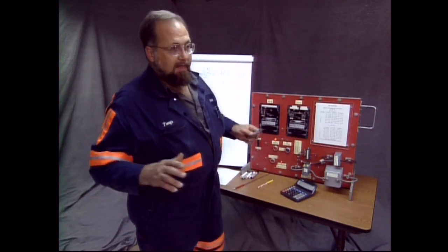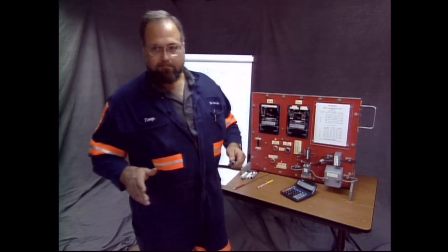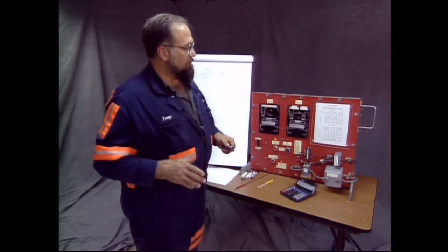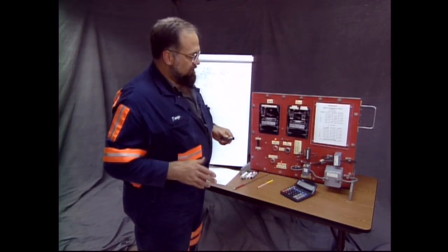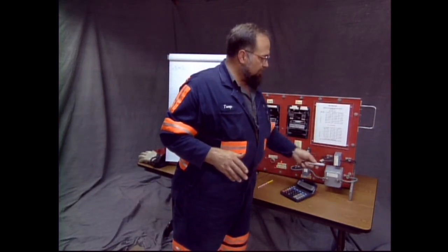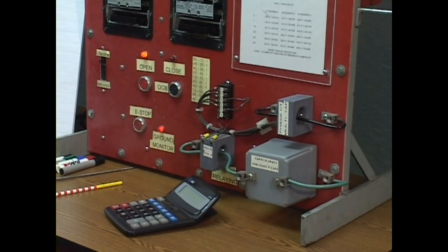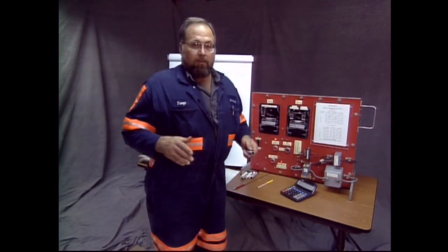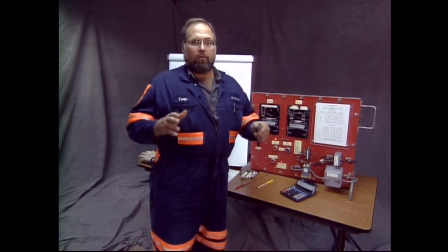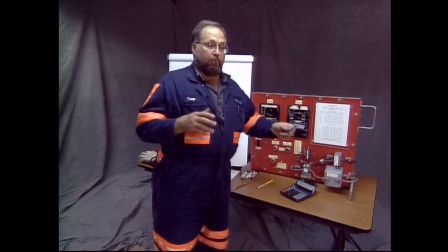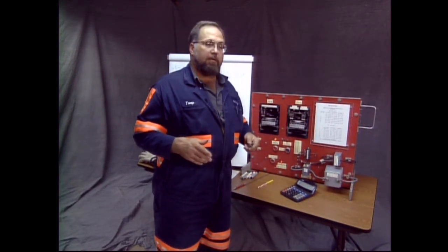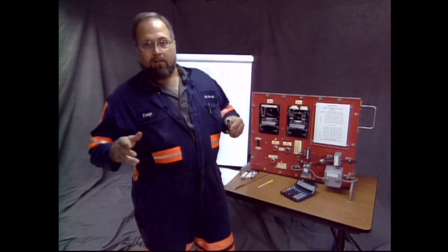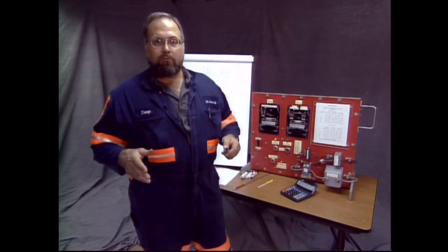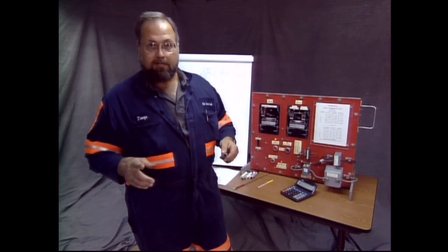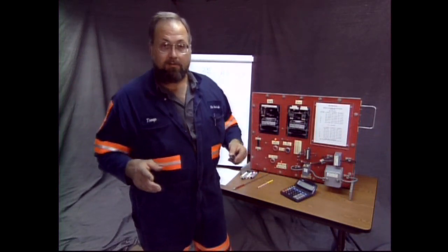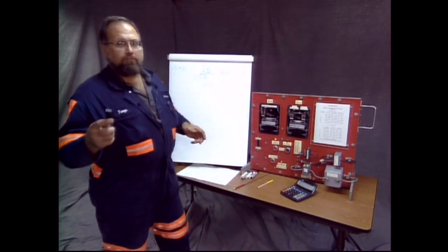Okay, fellas, now for the last bit of calculation, the last bit of figuring and math. We decided earlier that the ground resistor has to match the high voltage application here. The ground resistor needs to deal with at least one phase of your high voltage. If you had two phases grounded, that would be a short circuit, and this relay here would take you out. But the ground resistor needs to be able to convert the energy of one phase to heat. Now, it has to be appropriately sized. So we're going to do the calculation for the ground resistor.